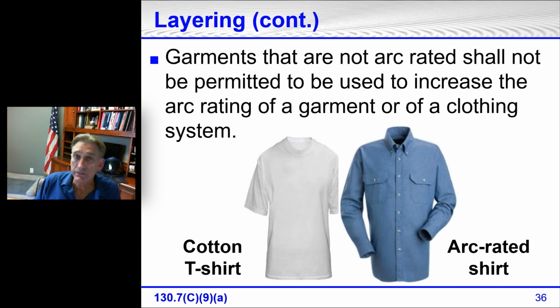Now, do they have clothing systems out there? Yes, absolutely. Bulwark, I've seen on their catalog online that when you buy a certain t-shirt with a certain shirt, it increases the value of the arc rating more than just adding the two pieces together. So in this case, will a cotton t-shirt add something? Yes, but we cannot add anything to the arc rating of that outer layer shirt. If it is 8.7, the maximum prospective incident energy that we can be in front of for a piece of equipment would be the rating of that shirt, which in this particular case, this is my shirt, and it's 8.7.